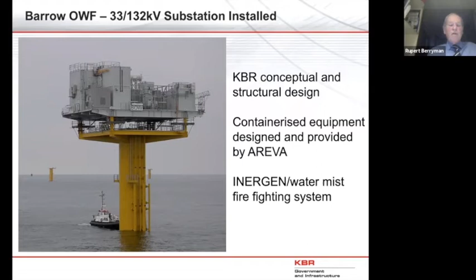So there are 4 array 33 kV cables coming into the substation and a 132 kV output cable going to Heysham switchyard. On the right-hand side of the transformer is the 132 kV switchgear. And for firefighting, it had an INERGEN water mist system, similar to the ones that you put into a ship. And for that, of course, we had to have a freshwater tank because they don't use seawater.